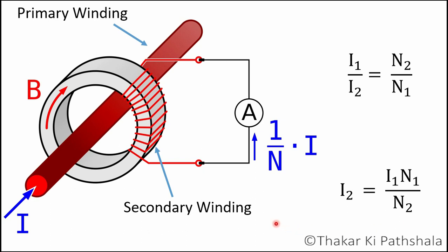Sometimes manufacturers indicate a current ratio to represent the range of the transformer. For example, a 500:5 rating indicates that this transformer steps down current from primary to secondary by a ratio of 500 to 5 — meaning if we measure 5 amperes on the secondary side, there should be 500 amperes flowing in the main circuit.